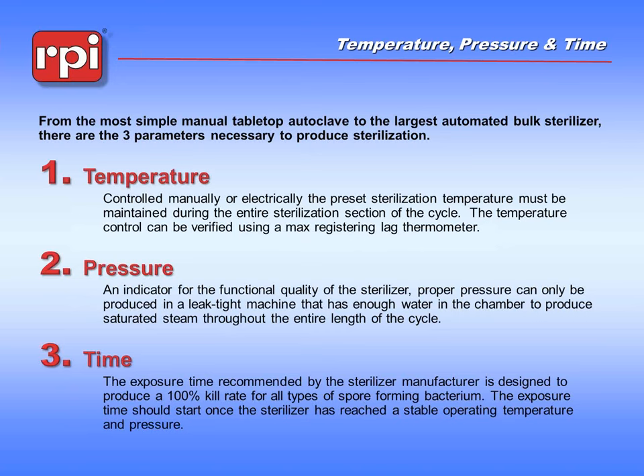In order to do that, we need a good conductor of heat as well as energy. Steam is the ideal conductor — it's very penetrating, and it can hold a lot of energy and transfer it very uniformly. You can also sterilize using just dry heat, but in order to do that you would have to increase the exposure time and increase the temperature, which limits the style of instruments that can be dry sterilized.